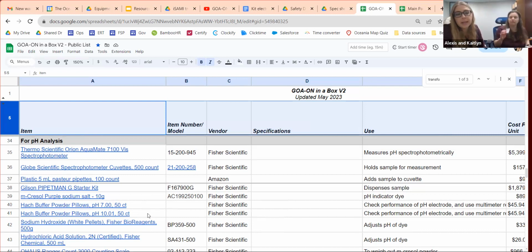We're still working on the guidance for using this to calibrate or to get an understanding of how the pH electrode is working, so you can properly adjust the pH of your dye solution. You might remember when we were at USP, they already had a pH electrode that we were able to use. We can use the one in the kit used for total alkalinity. We just need to understand how it's performing first.